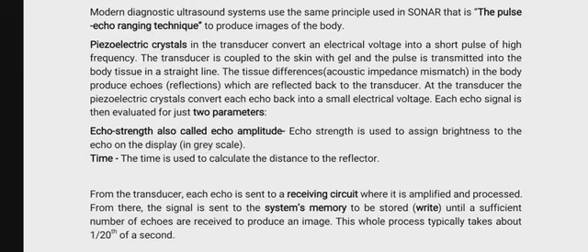Now understand what is happening here. Your normal transducer has piezoelectric crystals. These crystals are materials that change their forms mechanically based on voltage change. So what happens is that when voltage is applied to some of them, ultrasound is produced. Now some are in that same array to receive vibrations from the returning sound, which triggers generation of voltage and so on.